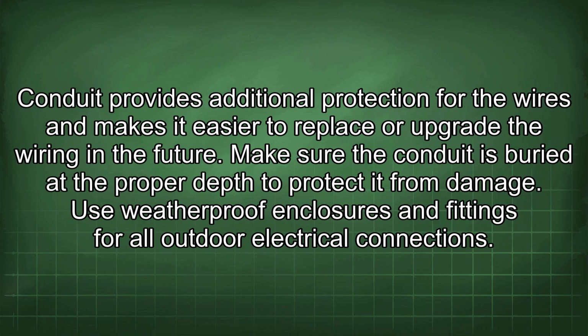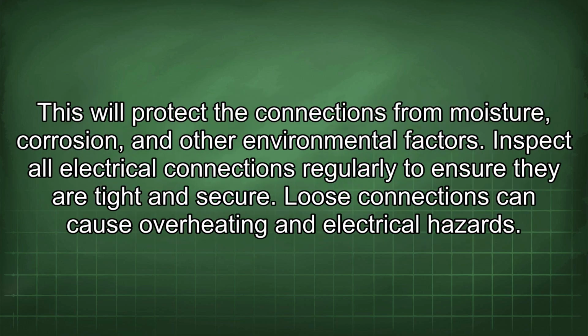Conduit provides additional protection for the wires and makes it easier to replace or upgrade the wiring in the future. Make sure the conduit is buried at the proper depth to protect it from damage. Use weatherproof enclosures and fittings for all outdoor electrical connections. This will protect the connections from moisture, corrosion, and other environmental factors.